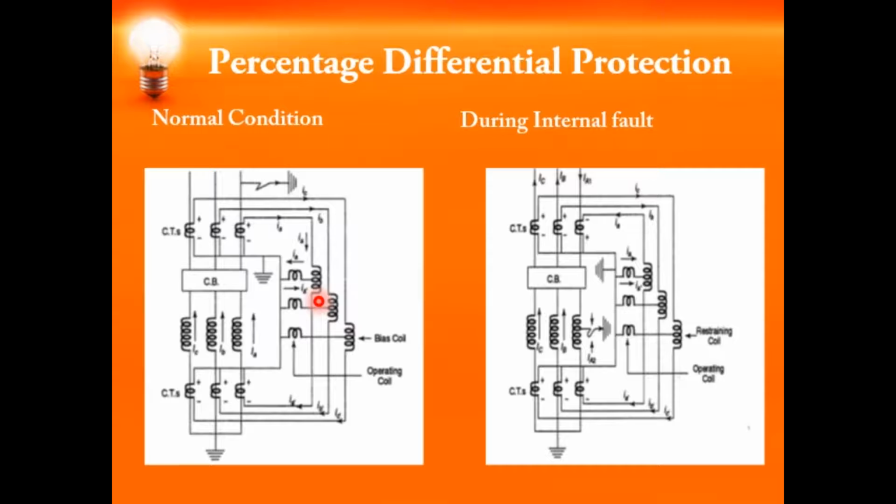In the case of stator faults, tripping the circuit breaker to isolate the faulty generator is not sufficient to prevent further damage, as the generator will still continue to supply power to the fault. Therefore, the percentage differential relay initiates an auxiliary relay, which in turn trips the main circuit breaker, shuts down the prime mover and the turbine, and generates an alarm. That is how you can prevent the generator from being damaged.